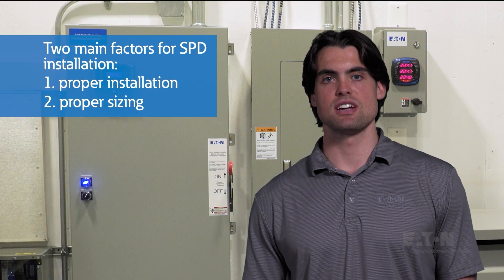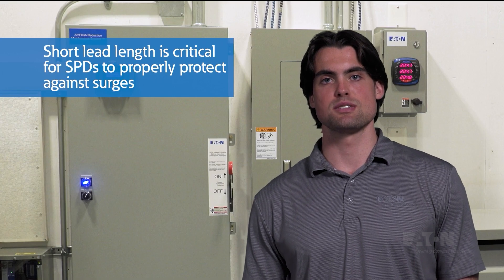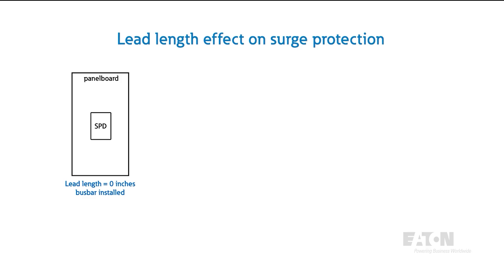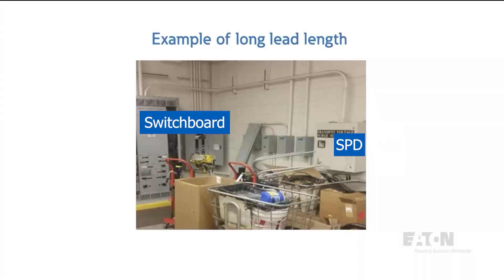There are two main factors in getting the most out of an SPD: proper installation and proper sizing. There are requirements for the breaker or fuse that the SPD connects to and a minimum wire size, but we strongly recommend installing SPDs with the shortest lead length as a best practice. This gives you the smallest amount of let-through voltage, offering better protection to your load center, MCC, switchboard, or switchgear. In our test setups with three identical SPDs at different lead lengths, the bus-connected SPD with zero lead length clamps at 350 volts, the one mounted 12 inches from the bus clamps at 550 volts, and the one just three feet away lets through almost 1,500 volts. In some real-world locations, we've seen them mounted more than 20 feet away — in that case, we'd recommend not even bothering to install an SPD, because it's not going to help you.